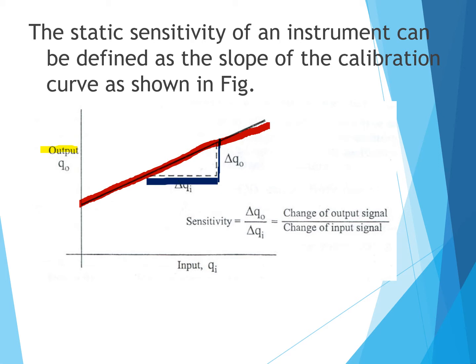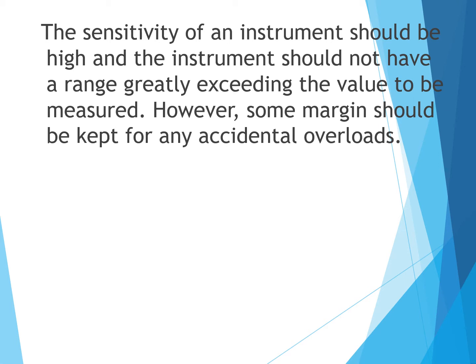In other words, sensitivity equals change in output signal divided by change in input signal. The sensitivity of an instrument should be high, and the instrument should not have a range greatly exceeding the value to be measured.